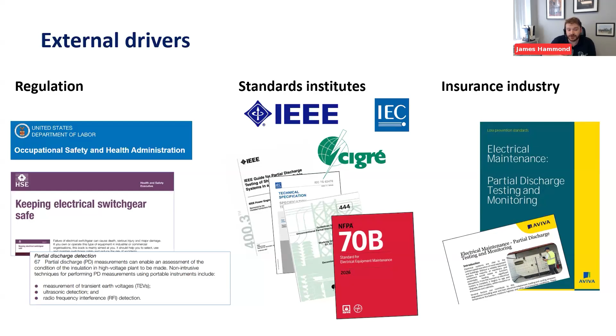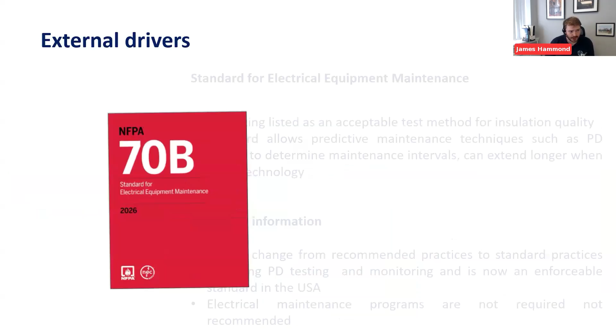We also see a huge demand in the insurance industry, basically requiring PD testing to actually be carried out. It's always worth checking policies for this, because sometimes it can say they completely void insurance if PD is not being tested, because it should be a method to understand asset health. It's similar to getting your car checked or your tire pressures checked. If that's not being done, there's a chance there could be further faults or damage that in some cases insurance companies wouldn't cover for.